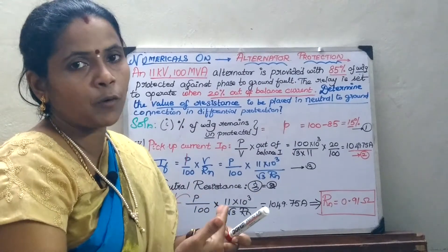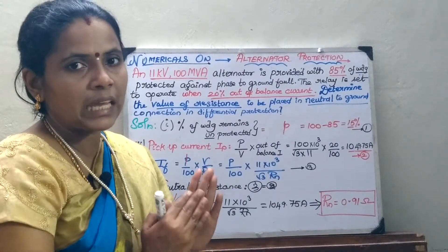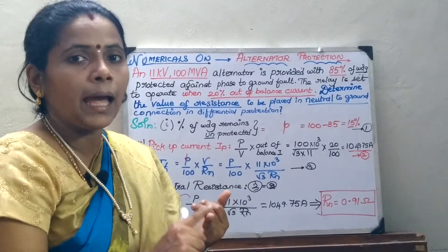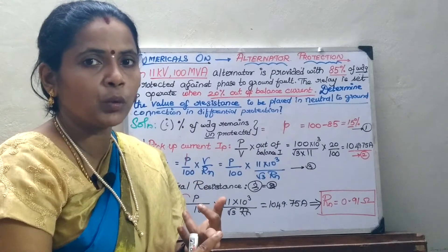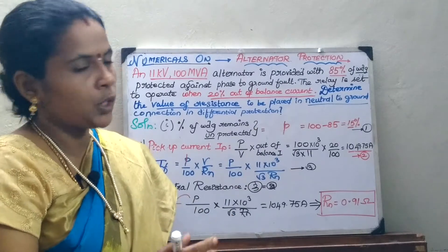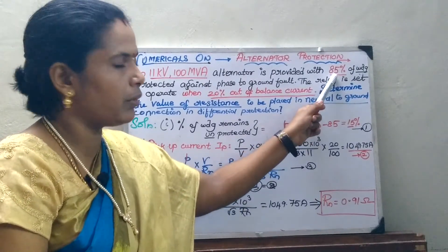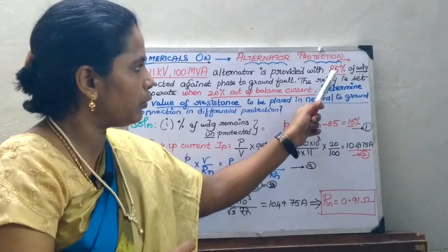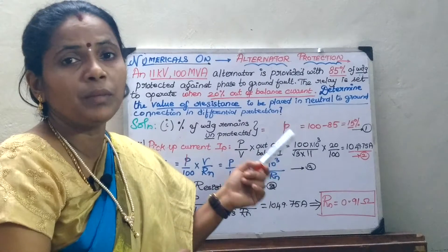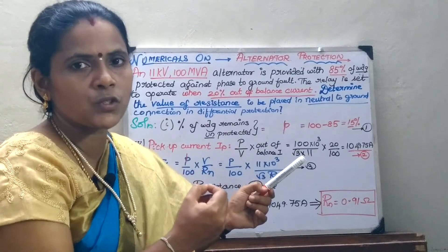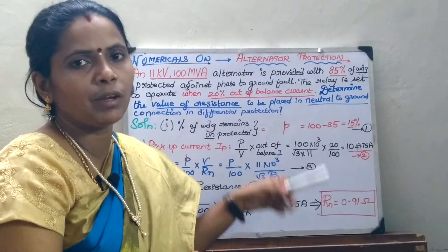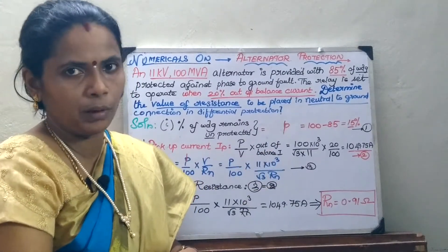The difference between the previous problem and this problem is: same rating of the alternator, but in the previous problem they gave the CT ratio and the out-of-balance current, and asked us to compute the percentage of the winding protected. Whereas here that value — 100 minus P — is given, and we are asked to calculate Rn. In the previous problem, the alternator was grounded through a neutral resistance of 5 ohms. So only the variables and parameters are changing.